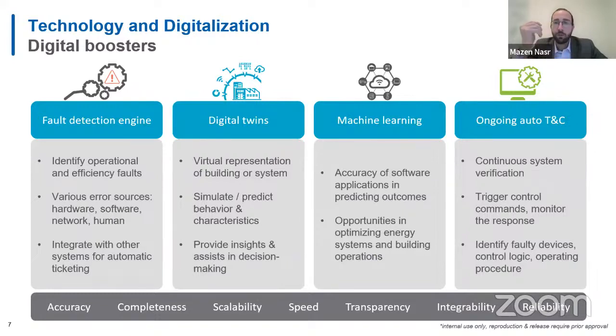A very simple example: at nighttime when the air handling unit is turned off, we could trigger a change of setpoints. I put the setpoint at 18 degrees and see how the unit reacts. Does the chilled water valve open? Does the fan speed up? What's happening with your dampers, etc.